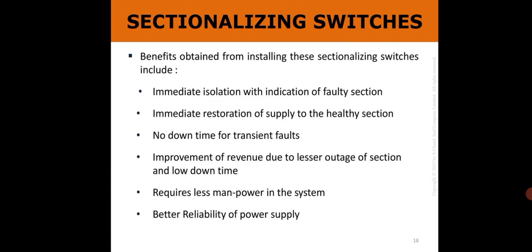Benefits obtained from installing these sectionalizing switches include immediate isolation with the indication of faulty sections. Next is immediate restoration of supply to the healthy sections. No downtime for transient faults. Improvement of revenue due to lesser outage of a section and low downtime. Requires less manpower in the system. Better reliability of power supply.